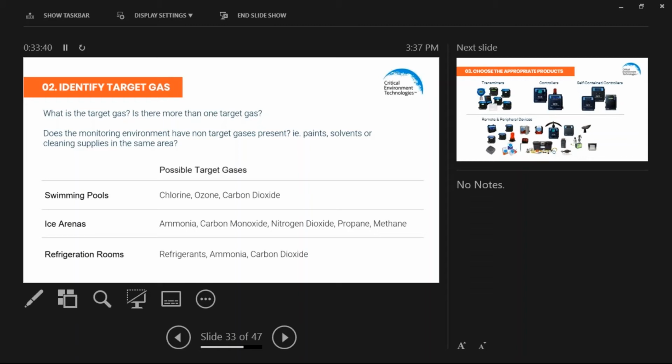There's no gas sensor for chloramines. Chloramines are created by overchlorinated water in conjunction with the high humidity levels in the envelope above the pool water, and the amount of activity, the amount of people, because it's a certain amount of natural bodily fluids that assist in causing the levels of chloramines to rise.